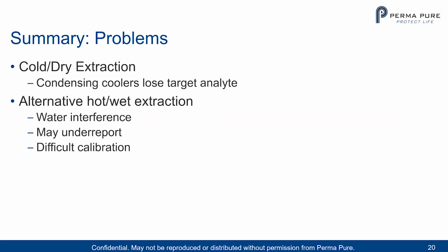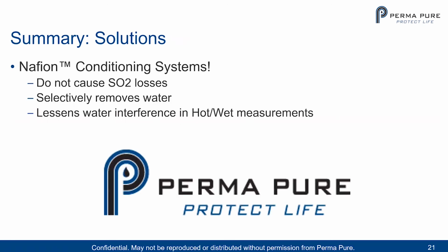So in summary, it really points to the Nafion dryer being the ideal way to dry your sample gas to preserve your SO2 measurements. So that's really what the end result is. Nafion systems do not cause SO2 losses, selectively remove water, and lessen water interference in hot-wet measurements.